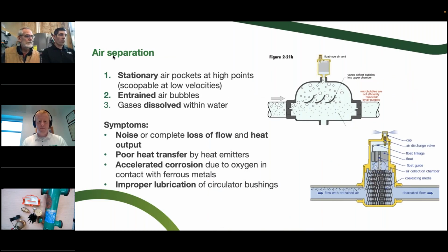Okay, so what type of air are we trying to separate? Stationary air pockets at high points are a great spot for a vent. That might be on the top of a heat exchanger for a boiler already, or in a radiator or something like that. That's a pretty easy one compared to the other topics. Entrained air would be like that milky look you have in a glass of water when you pour a glass of water from your kitchen sink. That is going to be harder to catch, those little milky micro bubbles, as the fluid is moving really fast at 4-6 feet per second through a piece of pipe. That's not something that you're going to vent very well. That's going to go right through a scoop like this.